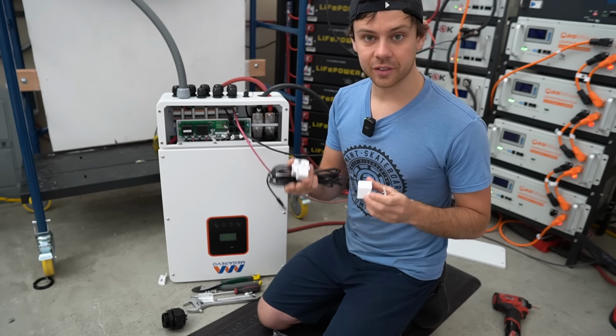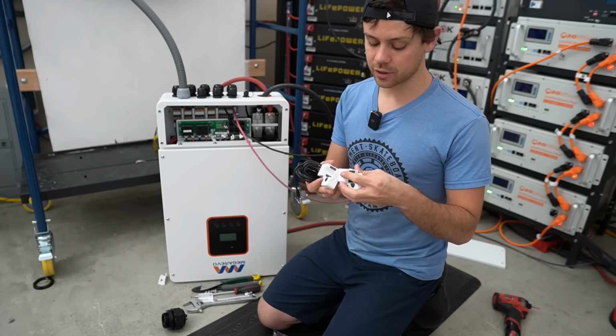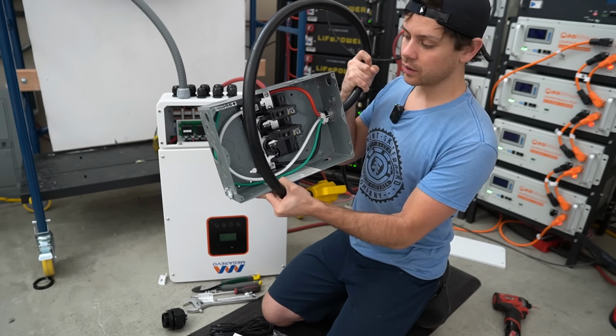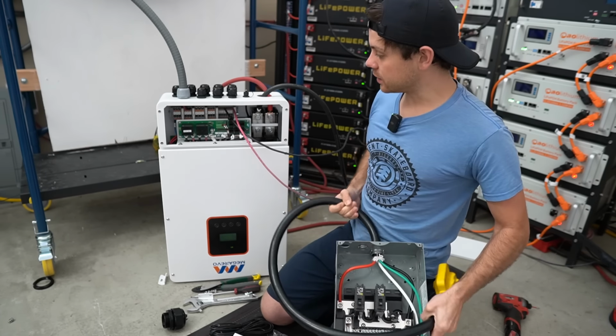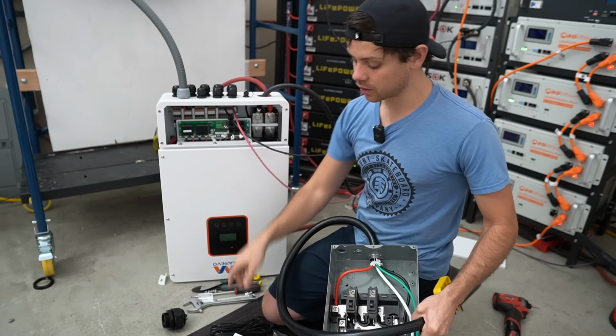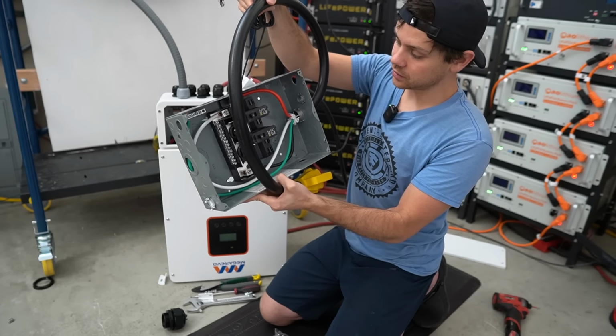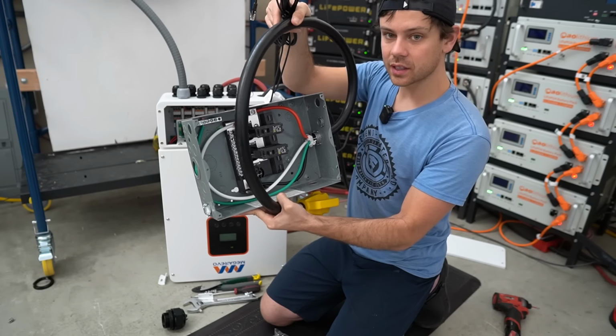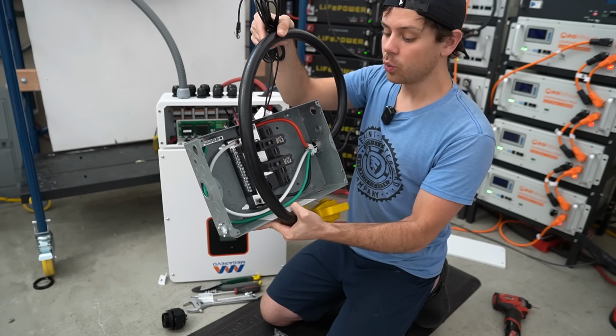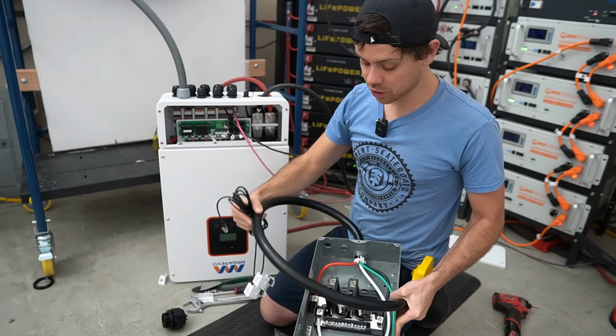The other ones were just floating around in the box that got damaged. Now we're gonna connect this load center to the grid, and then we're also gonna connect it to the AC input of this inverter, and then we'll add the CTs onto the supply. That way we can add loads to this and offset the loads without backfeeding the grid. So this should be really fun.